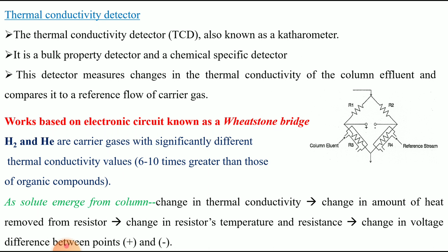It works mainly based on the Wheatstone bridge. In the Wheatstone bridge, 4 resistors are there, having similar resistance. The carrier gases generally used here are hydrogen and helium.